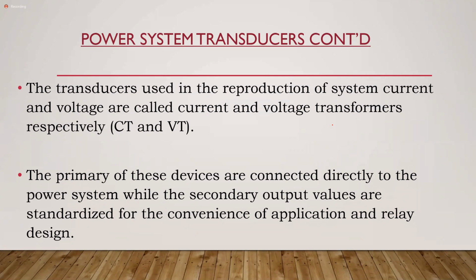And what are these standard values? For your CT, the standard output values for your CT are 1 and 5 amperes. Now, the 1 ampere was usually used in, well, based on the British standard. So you might find 1 ampere, yes, 1 and 2 amperes to be honest, from the British standard. So the BS standards would have your 1 and 2 and 5 amperes. The American standard, which is the ANSI standard, the standard output for your CT is 5 amperes.